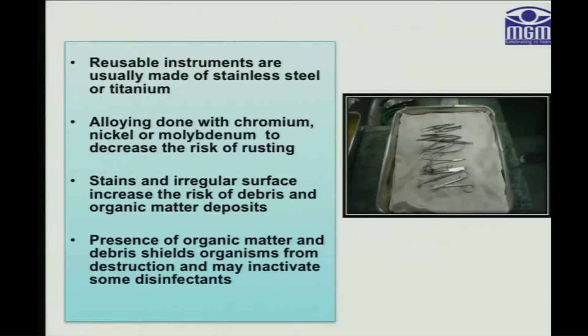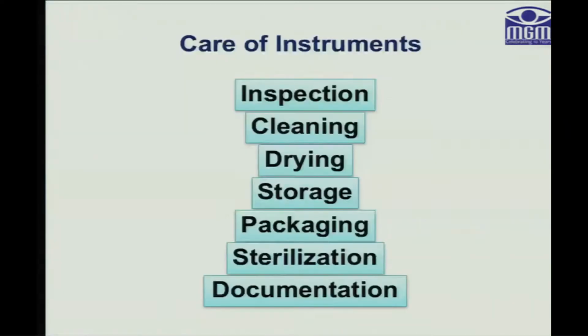Reusable instruments are usually made up of stainless steel or titanium, where alloying is done with chromium, nickel or molybdenum to decrease the risk of rusting. Stains and irregular surface increase the risk of debris and organic matter deposits. Presence of such may prevent the destruction and may inactivate some of the disinfectants.